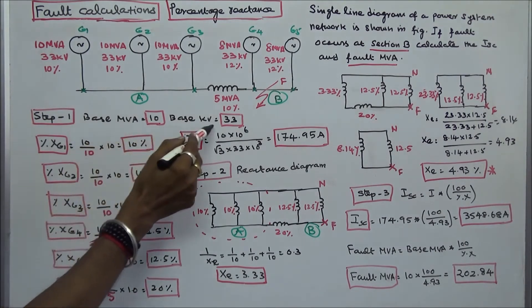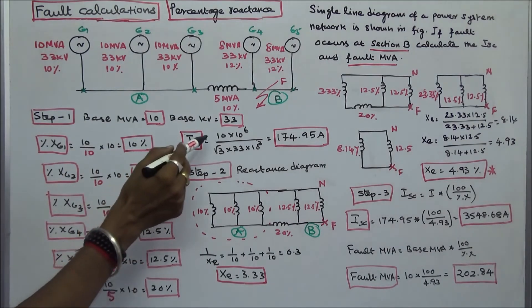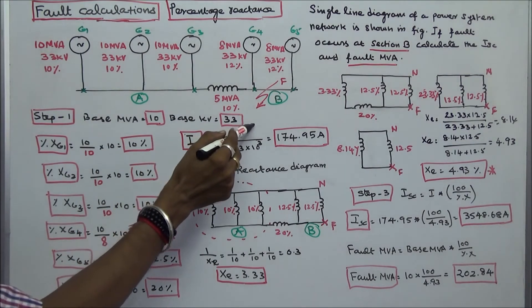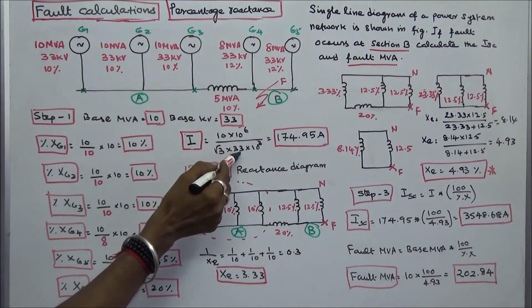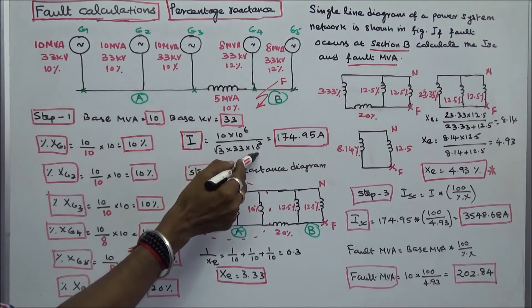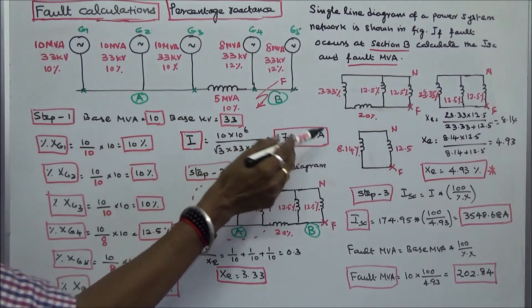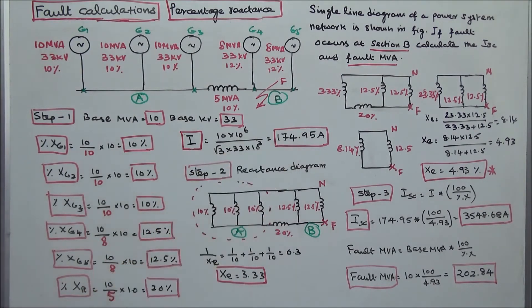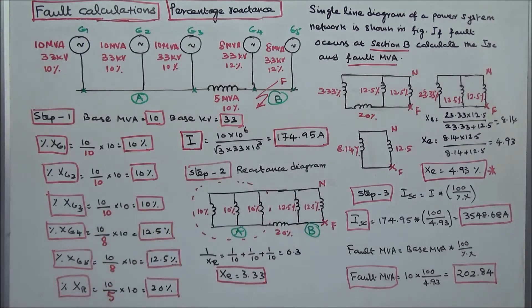Next, I have to calculate the base current I. Base MVA is 10, base kV is 33. I equals 10 × 10⁶ divided by (√3 × 33 × 10³), which equals 174.95 amps. Step 2: I have to draw the reactance diagram.